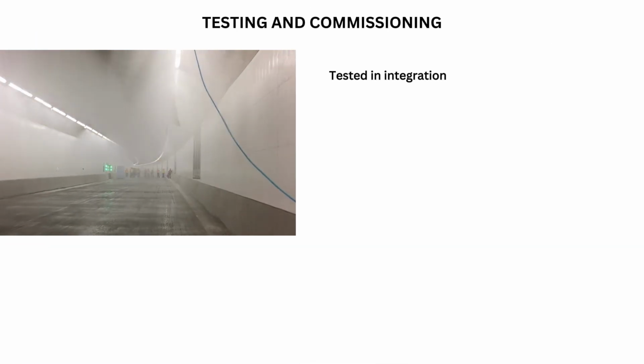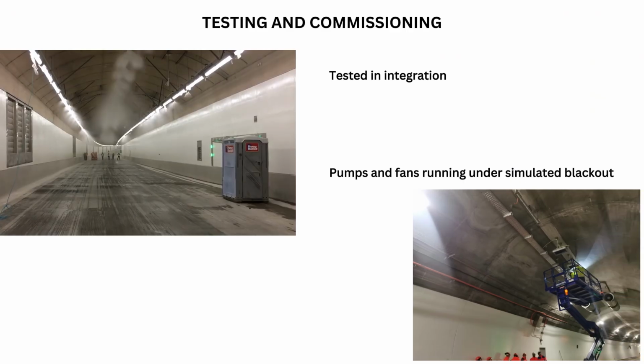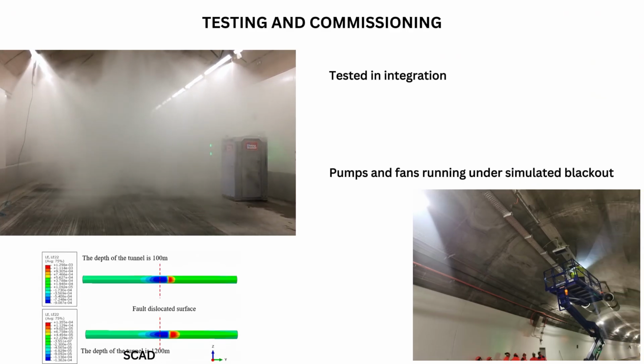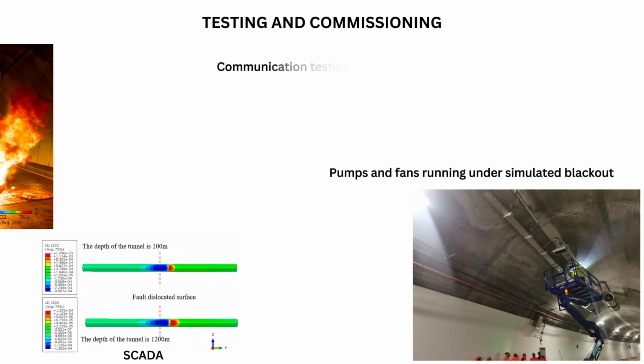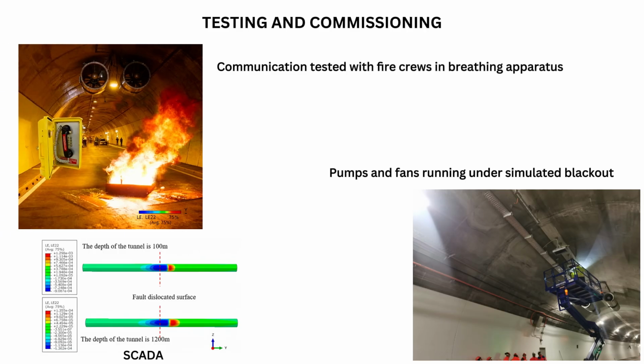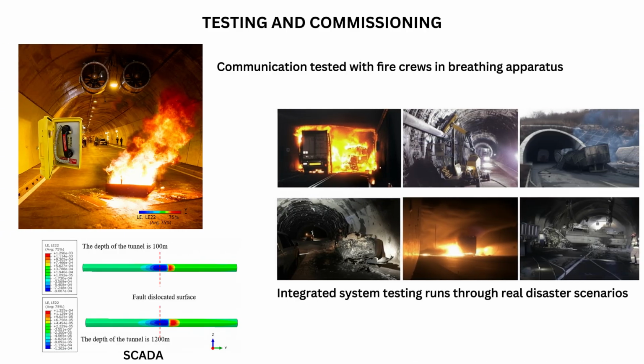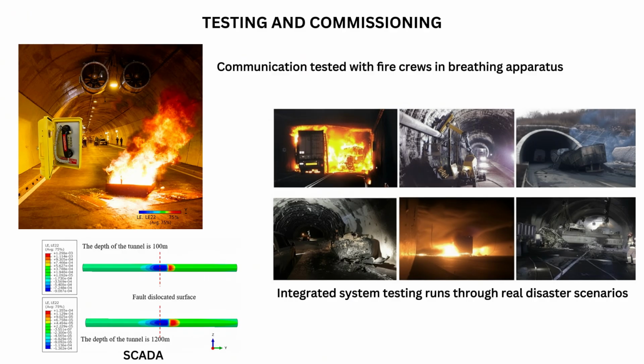Testing and commissioning. Every system is tested in integration. Pumps and fans running under simulated blackout. SCADA responding to injected faults. Communication tested with fire crews in breathing apparatus. Integrated system testing runs through real disaster scenarios, verifying that power, ventilation, communication, and control work as one machine.